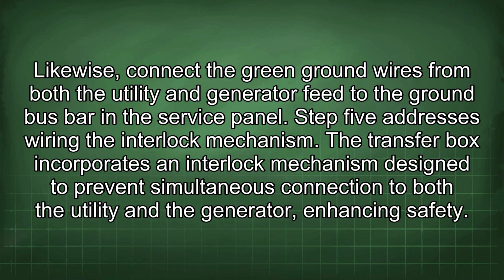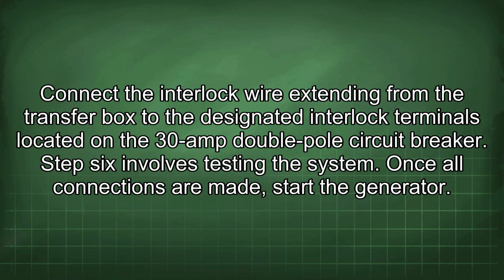Step 5 addresses wiring the interlock mechanism. The transfer box incorporates an interlock mechanism designed to prevent simultaneous connection to both the utility and the generator, enhancing safety. Connect the interlock wire extending from the transfer box to the designated interlock terminals located on the 30-amp double-pole circuit breaker.